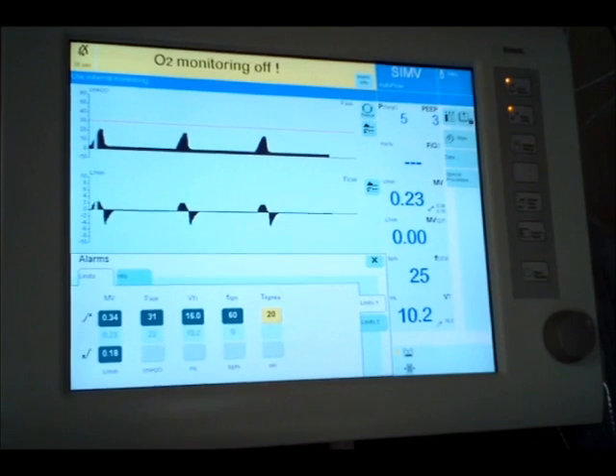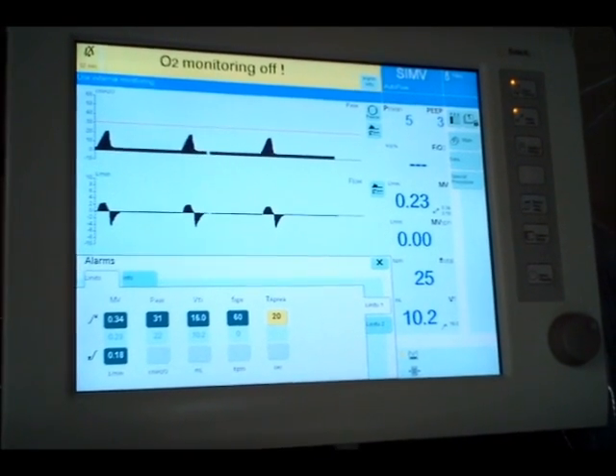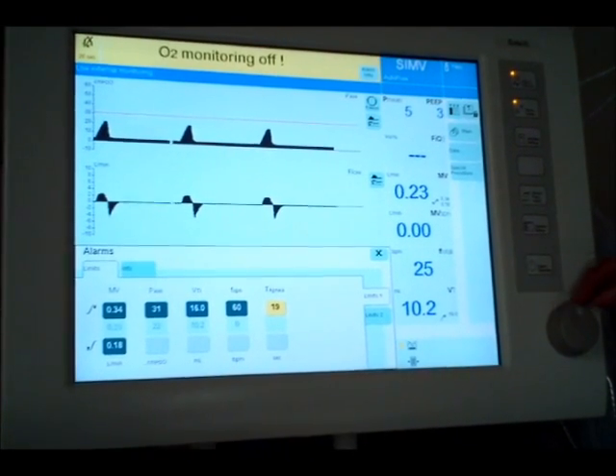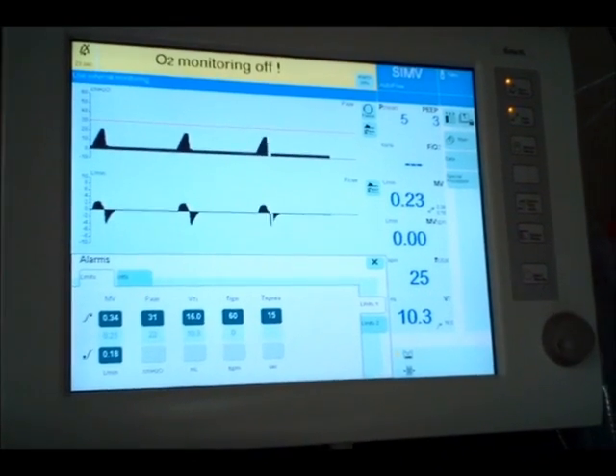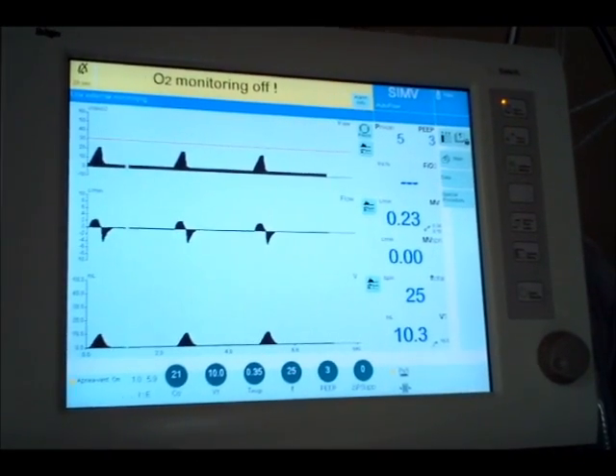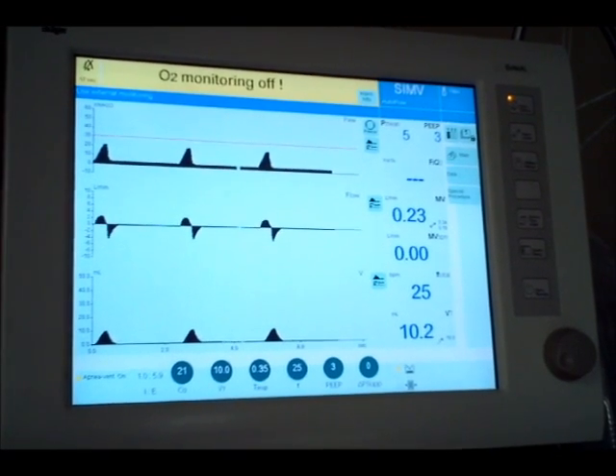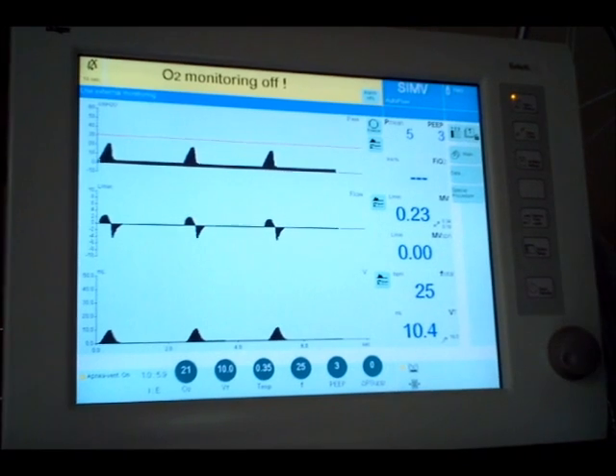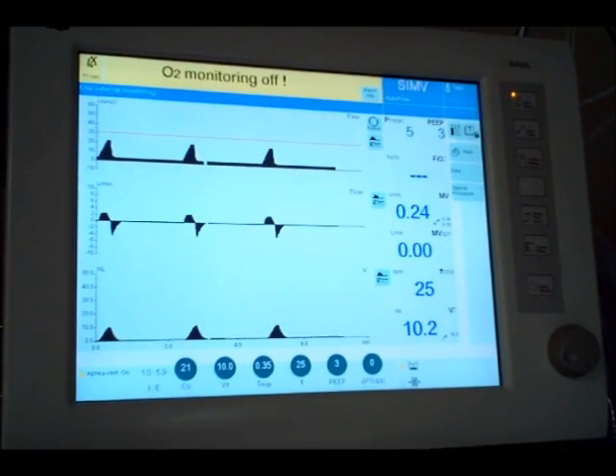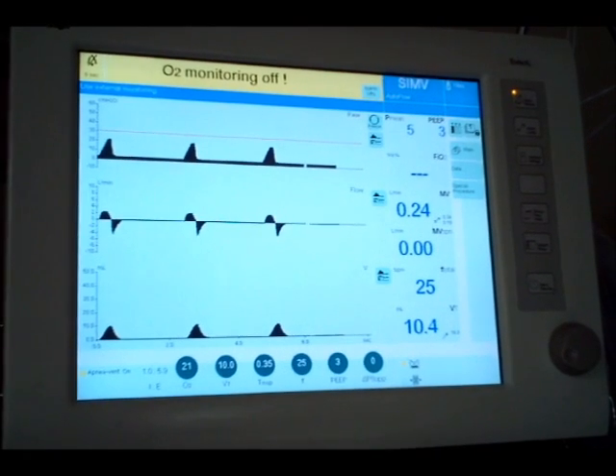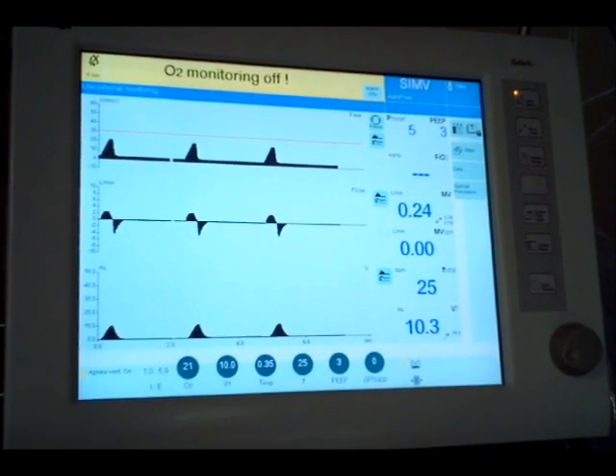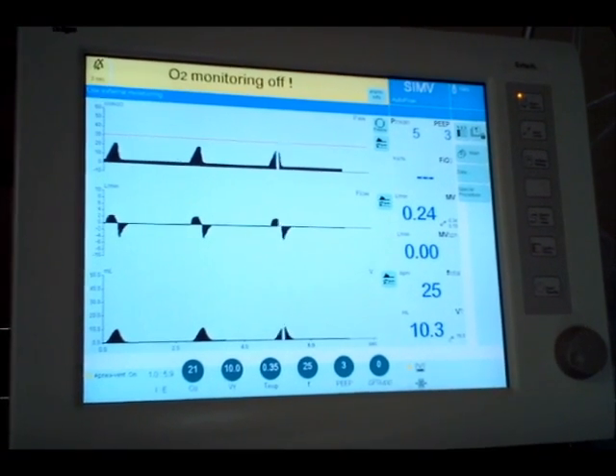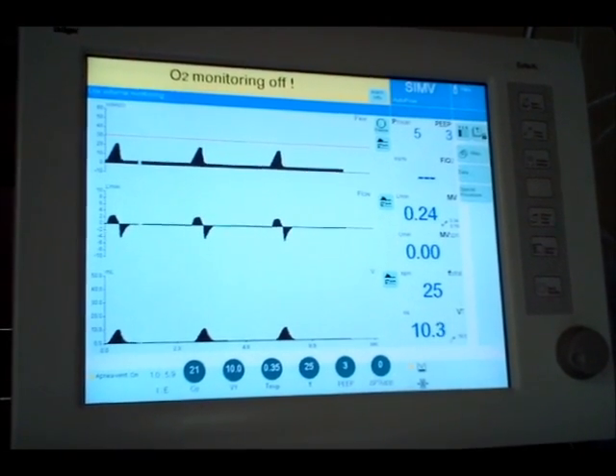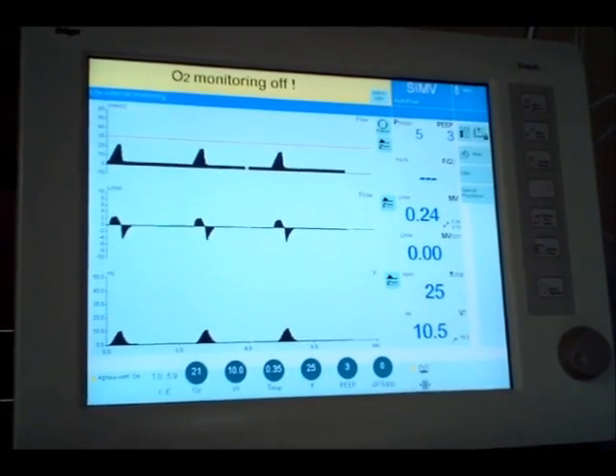Again, now our apnea time, this may be where we want to consider changing our apnea time. Theoretically, the baby should get a mechanical breath at least every 2.4 seconds, right? But just to be on the safe side, I think I'm going to go down to 15. All right, so when you make that switch from CMV to SIMV, there are some things you need to remember. Remember, set your apnea time. Remember, set your high breathing rate alarm. Okay? I think I had those starred before, and I wasn't comfortable with it.